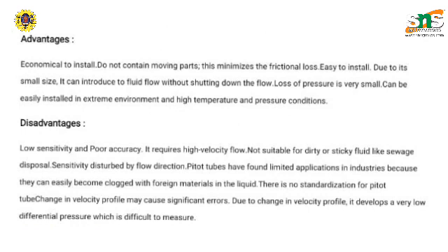So in this part, the Pitot tube is economical and is installed without containing moving parts, and this minimizes frictional loss and makes it easy to install. Due to its small size, it can be introduced to fluid flow without shutting down the flow, and the loss of pressure is very small. It can be easily installed in extreme environments and high temperature and pressure conditions.